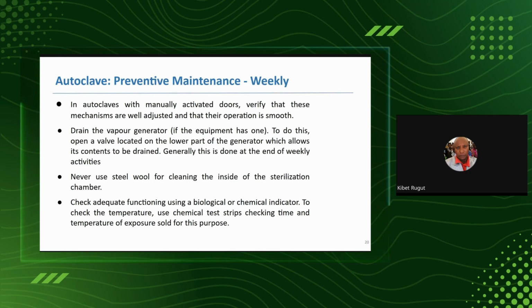So if those are manually activated, it is good to look that they are well adjusted and they operate smoothly. That is, the latch locks and opens. When the vapor is being released to the atmosphere after a cycle, most of the time it is good to check that it is doing its work well. It is clean. There's nothing that can cause it not to close back well, or that can cause it not to seal back after opening. Never use steel wool for cleaning the inside of this chamber.